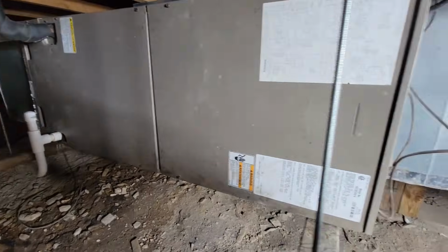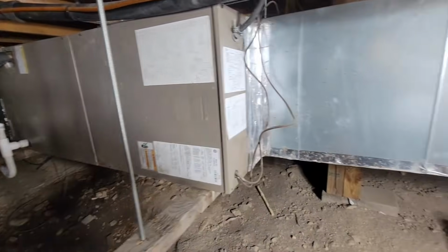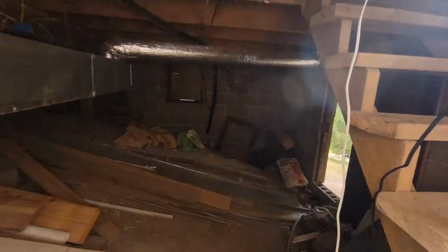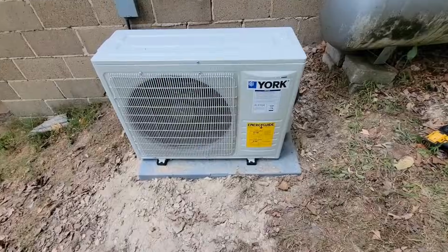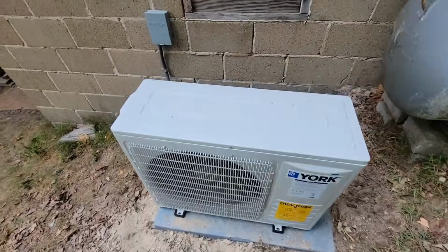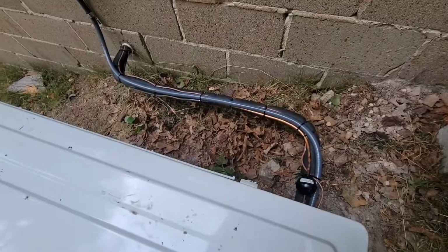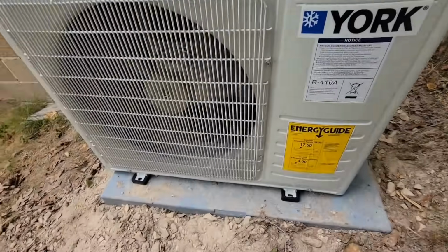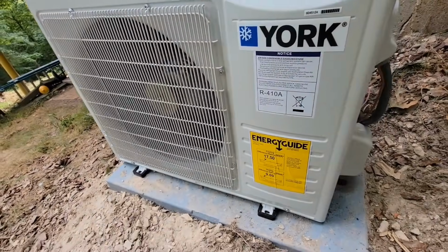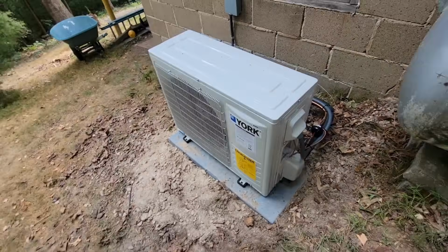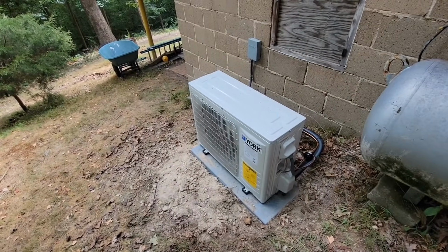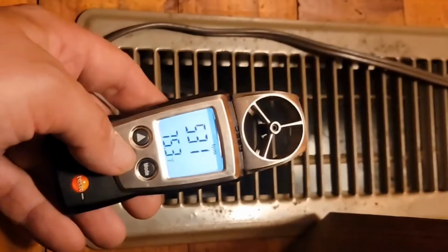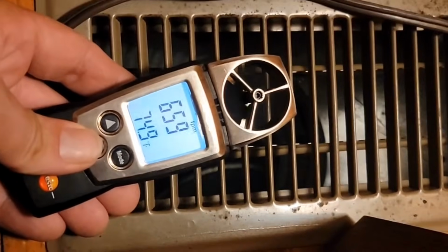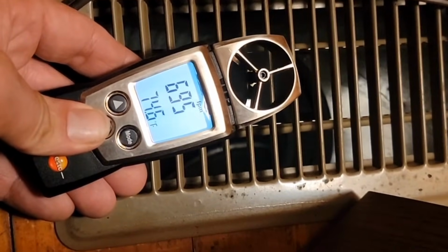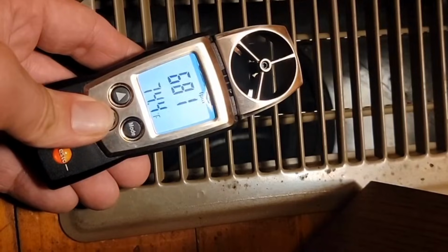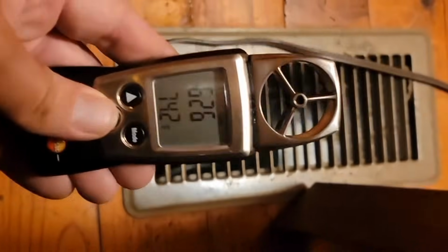All right, unit's on. Indoor air handler's buttoned up. We're gonna go inside and check some airflow now. Running 100%, and you can hear the sound. Super quiet. All right, checking the supply register. 650 feet per minute. That's nice.